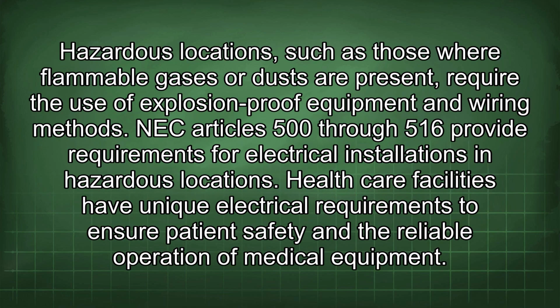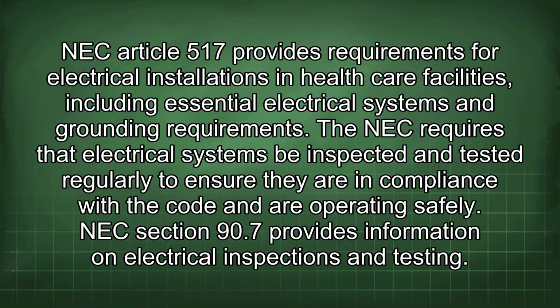Hazardous locations, such as those where flammable gases or dusts are present, require the use of explosion-proof equipment and wiring methods. NEC Articles 500 through 516 provide requirements for electrical installations in hazardous locations. Healthcare facilities have unique electrical requirements to ensure patient safety and the reliable operation of medical equipment. NEC Article 517 provides requirements for electrical installations in healthcare facilities, including essential electrical systems and grounding requirements.